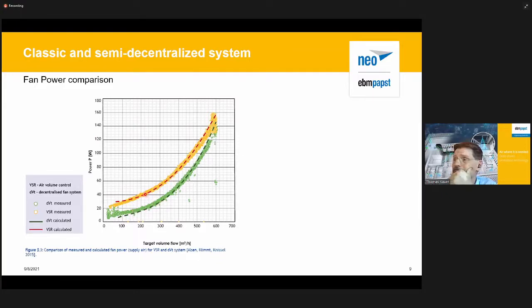So we can see, especially here, that if we are not at full airflow, we would not need full airflow in the system. As we know from the usage of the building, also during the Corona pandemic, there are very few people in the room. People tend to stay in home office, and only about half of the people are there. So we would typically run systems in not full performance, not full airflow mode. And what you can see here is that you start from here downwards to really get half of the energy that you use when using this decentralized system, compared to the energy that is wasted for the pressure differential around the flap.